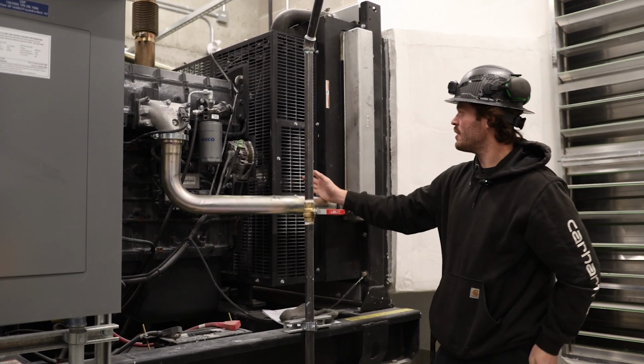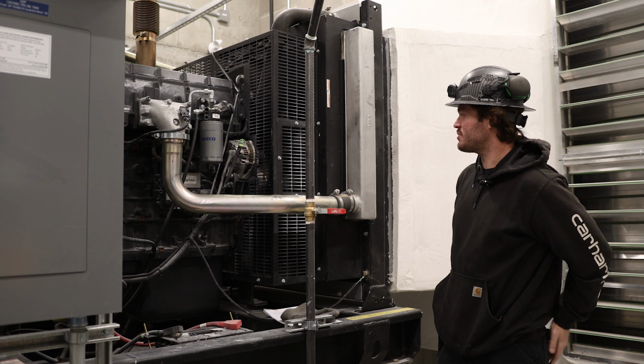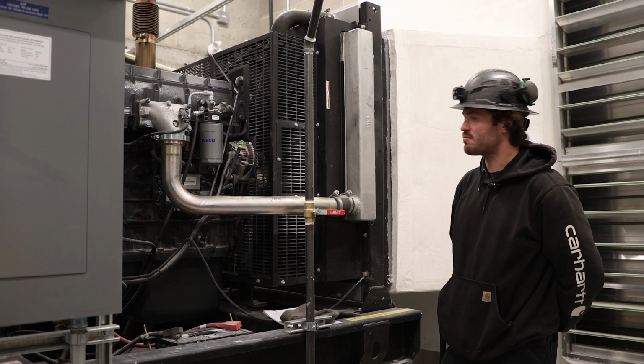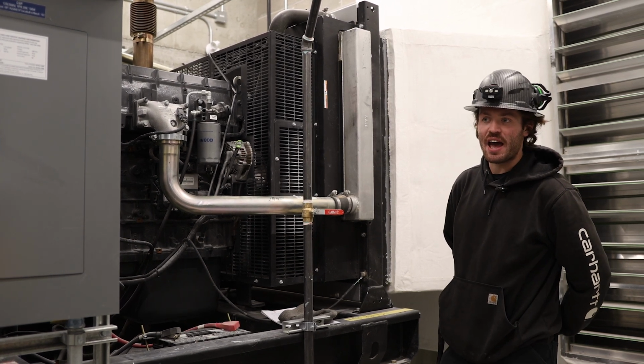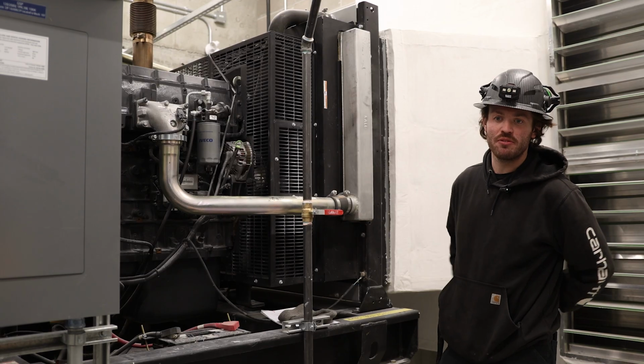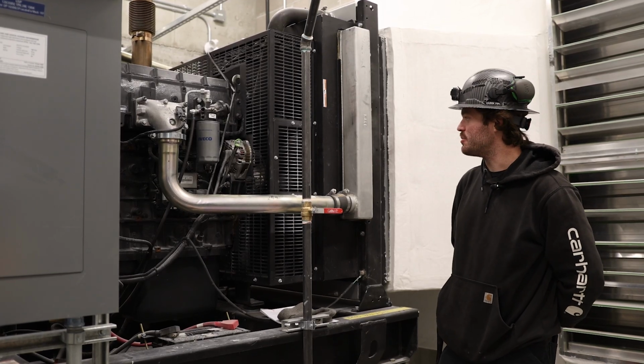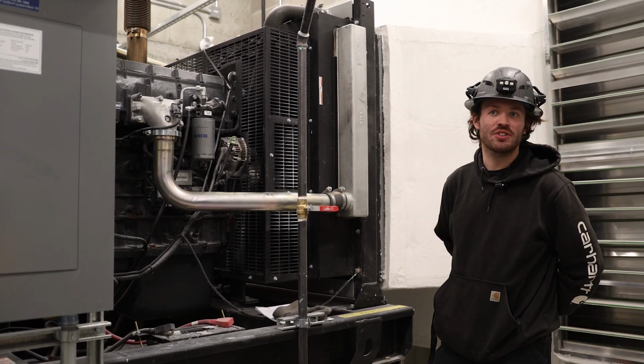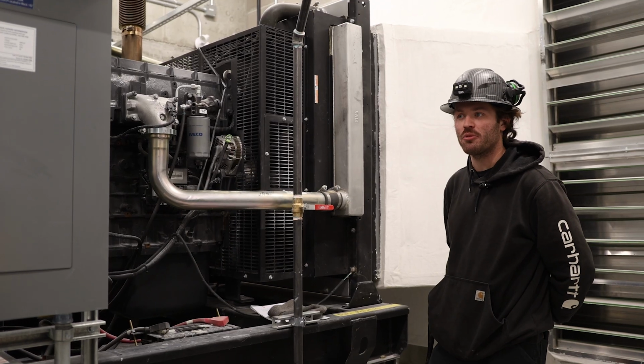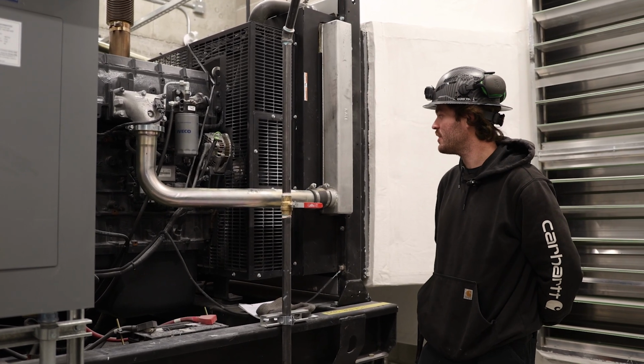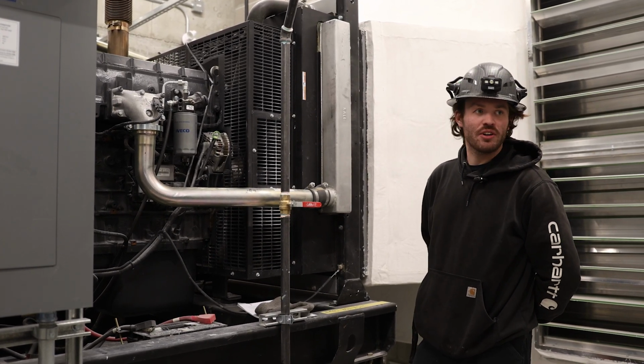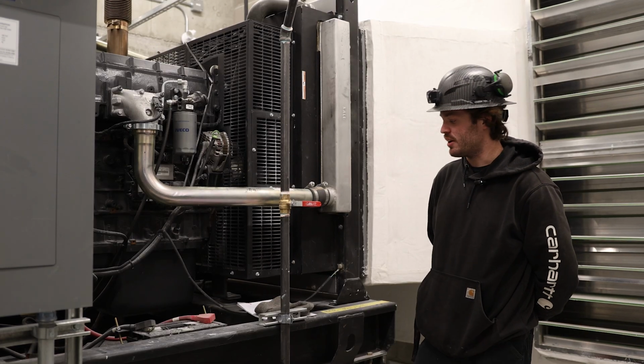On the front is where our drive belts for our accessories are. The belt doesn't necessarily have a service replacement date, but it's to be inspected and monitored for its condition, whether it's wearing improperly or if debris has gotten to it. Generally, they last a very long time because gen sets do not see a ton of run hours.